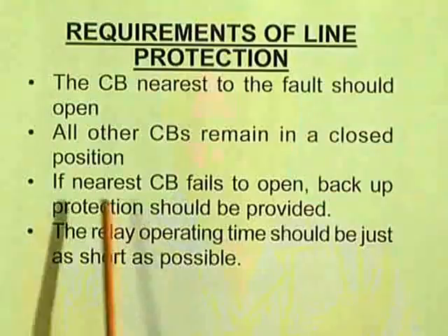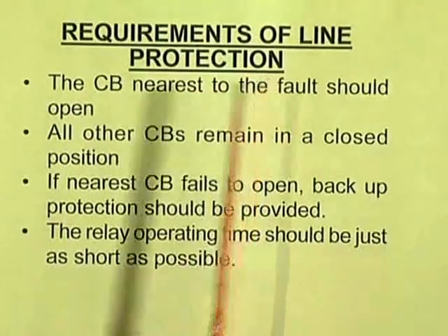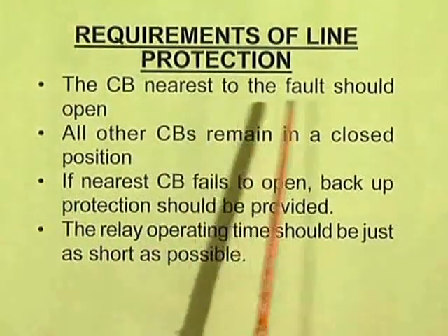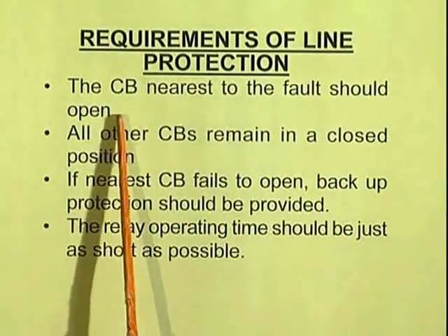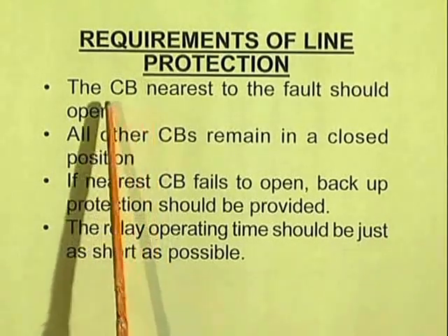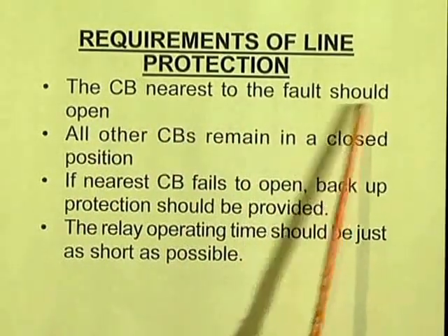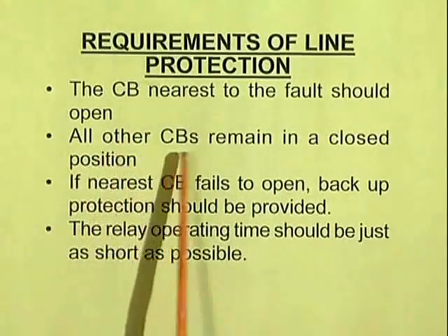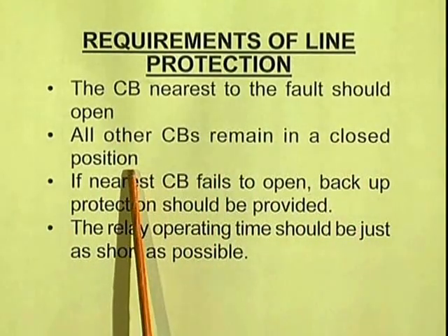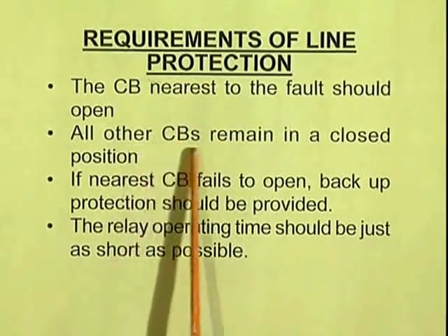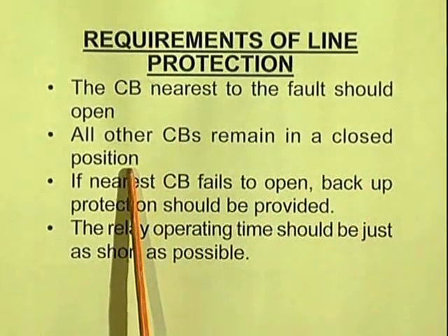The requirements of line protection. When we are talking about protection for lines, what must be the requirement for a relay? The requirements of line protection: the circuit breaker nearest to the fault should open. That means there are many circuit breakers all along the line, but the nearest circuit breaker should open for the fault. All other circuit breakers remain in the closed position. That means when one circuit breaker operates, the other circuit breakers should remain closed.